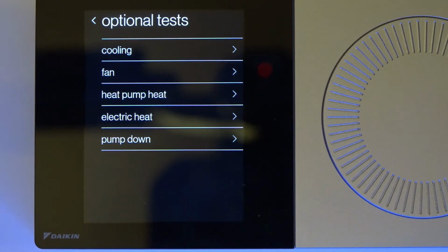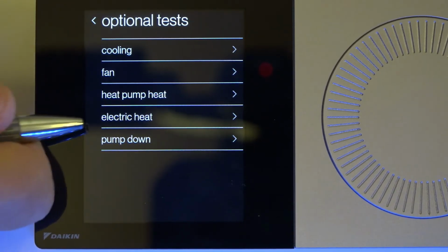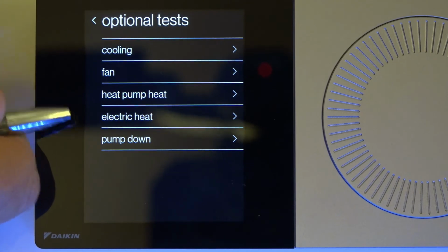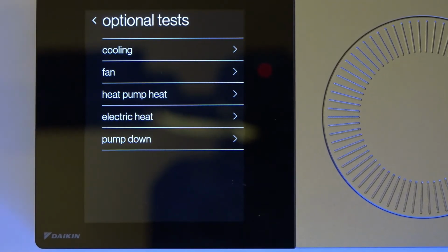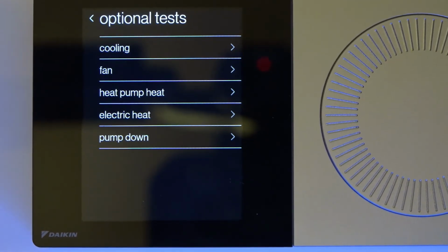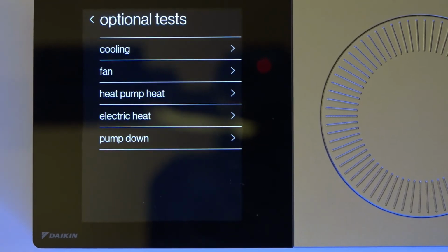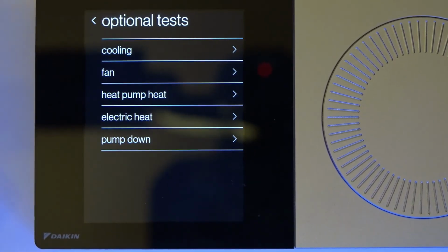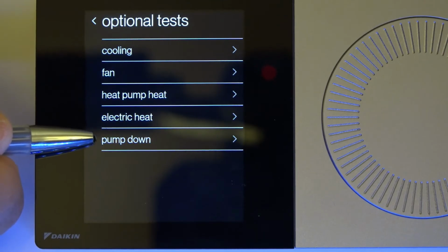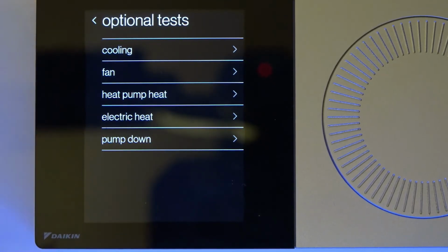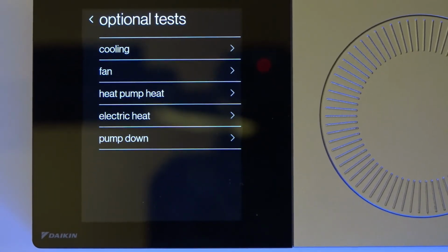I can turn the fan on and off, run the heat pump. I can go ahead and turn on the electric heaters, burn off any oils or anything like that that might have been on the heater kit from the factories. And if I ever need to pump the system down, I have to do it here. This is the only way to electronically bypass the low pressure transducer.